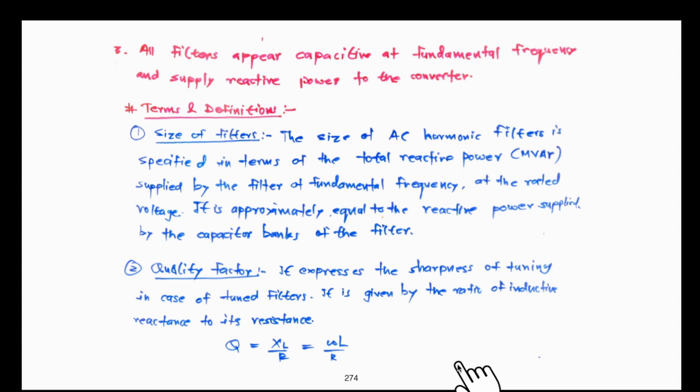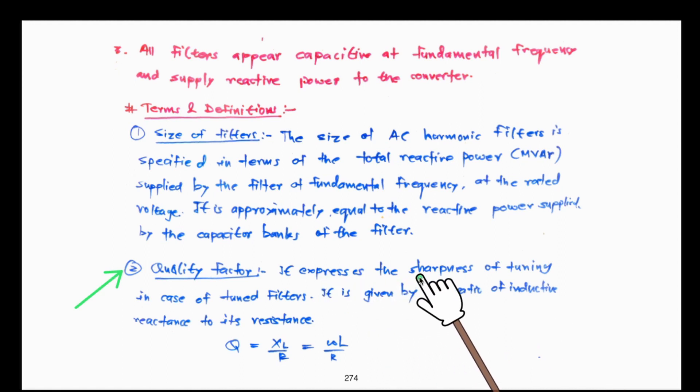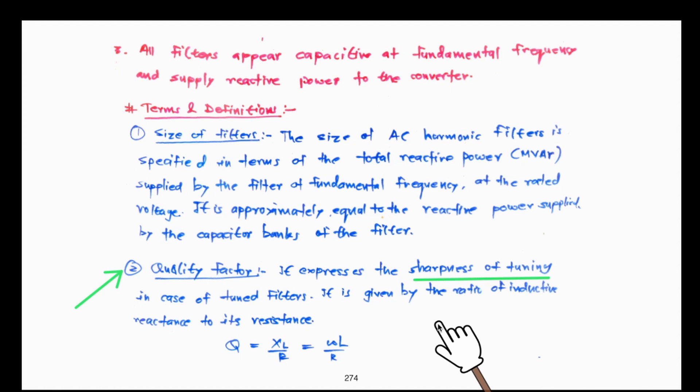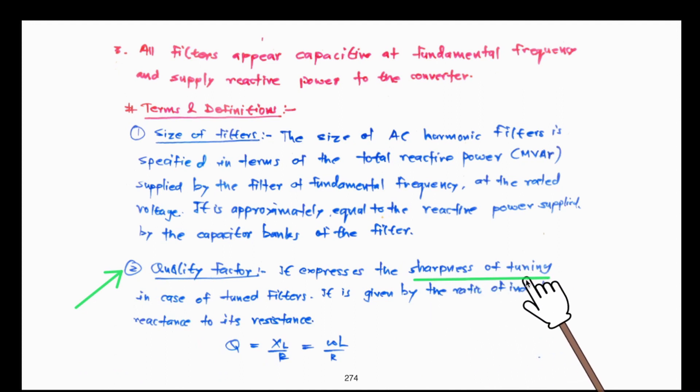The next important term is the Q factor or quality factor. Since we want to eliminate a selective frequency — say the 11th or 13th order harmonic — the quality factor of the filter expresses the selectiveness or sharpness of tuning. The filter is connected in the circuit to eliminate the 11th harmonic; how precisely the filter selects that particular frequency and eliminates it by providing a low impedance path is determined by the Q factor.